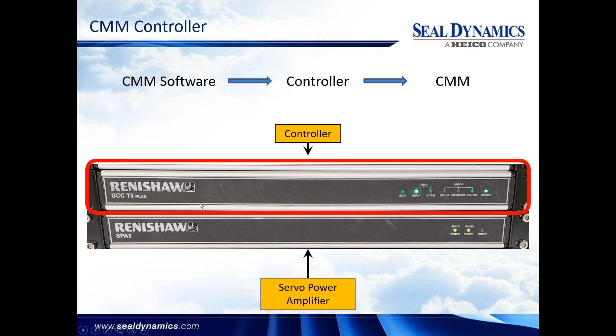In our case, as I showed you earlier, this is our controller. It's got various lights, and depending on if they're lit up or blinking, it tells you if something's wrong or not. Technically, the top part is the control, and the bottom part is a servo power amplifier. But when they work in conjunction together in unity, they're controlling all the components of the CMM. Often, if you have a problem with your CMM and you have to talk to tech support, they're going to want to know what kind of controller you have. So it's important you understand how all that works and at least what kind of controller you have. In this case, it's a Renishaw UCC T3+. That's important to know.